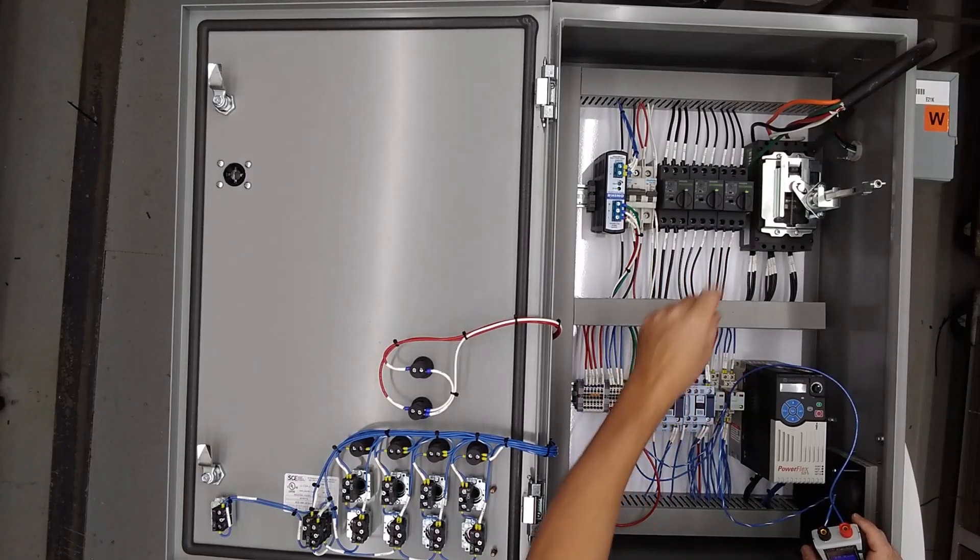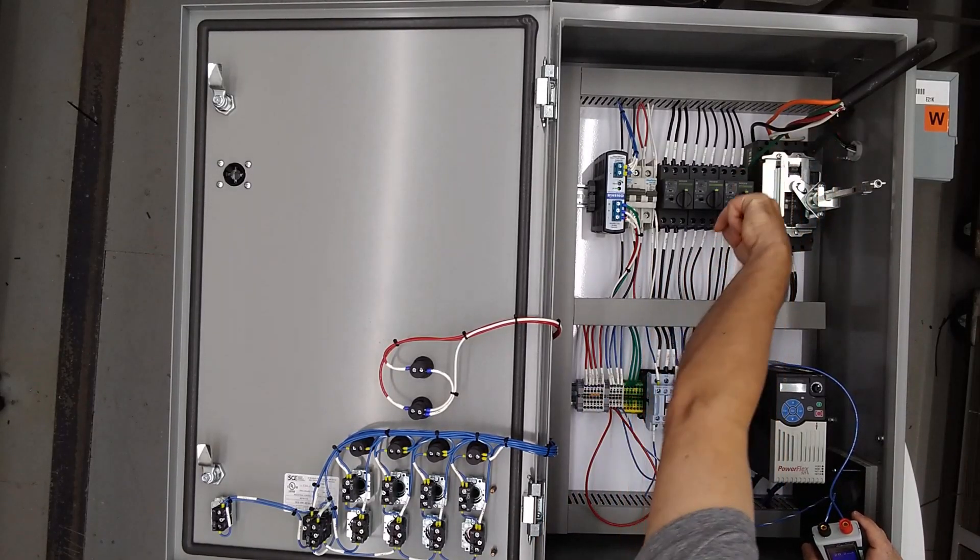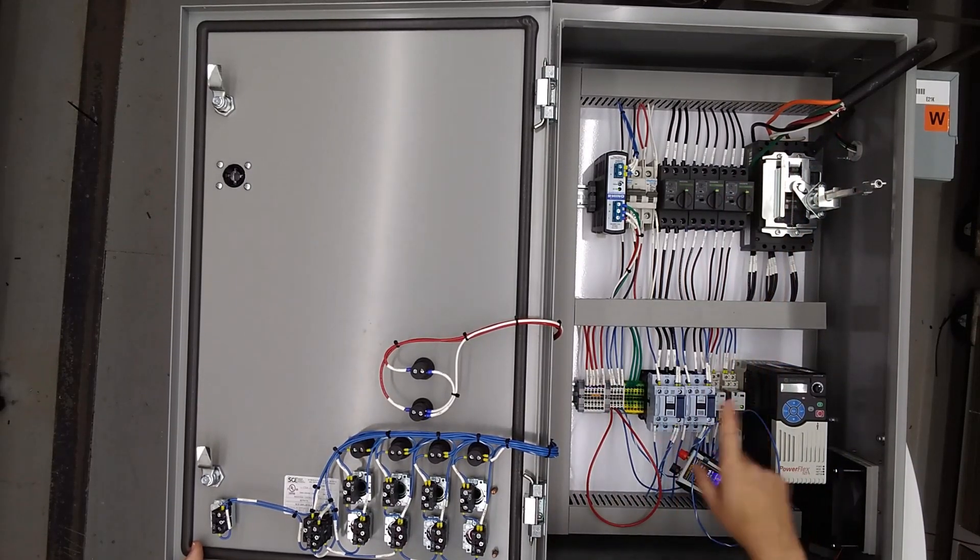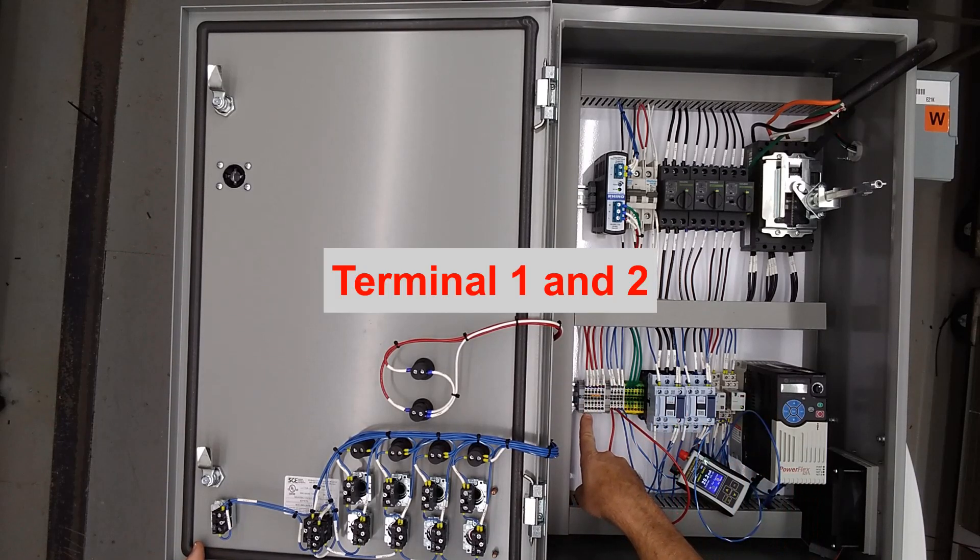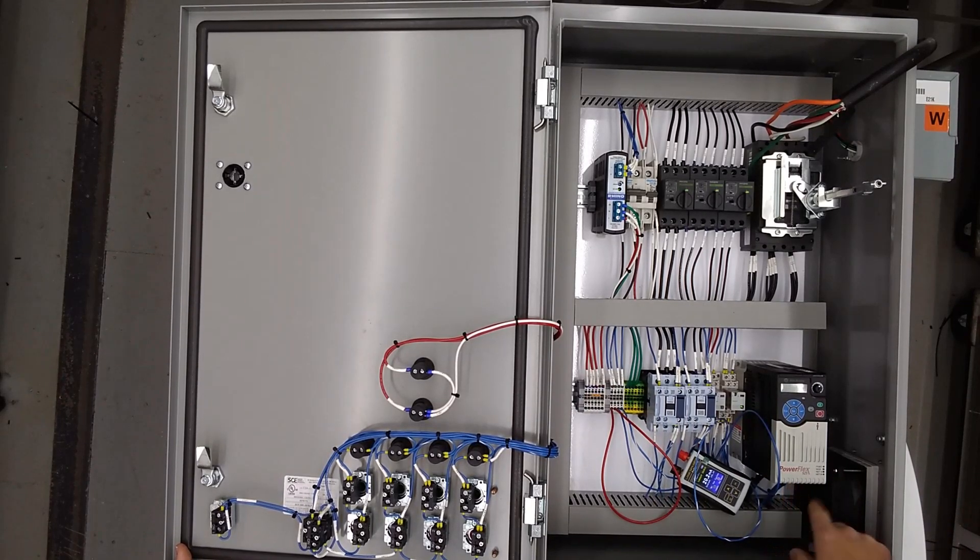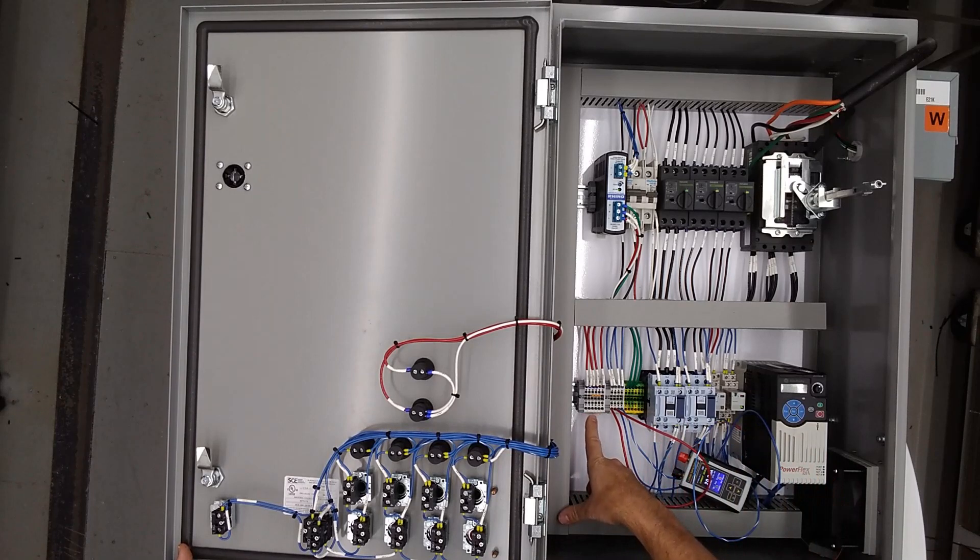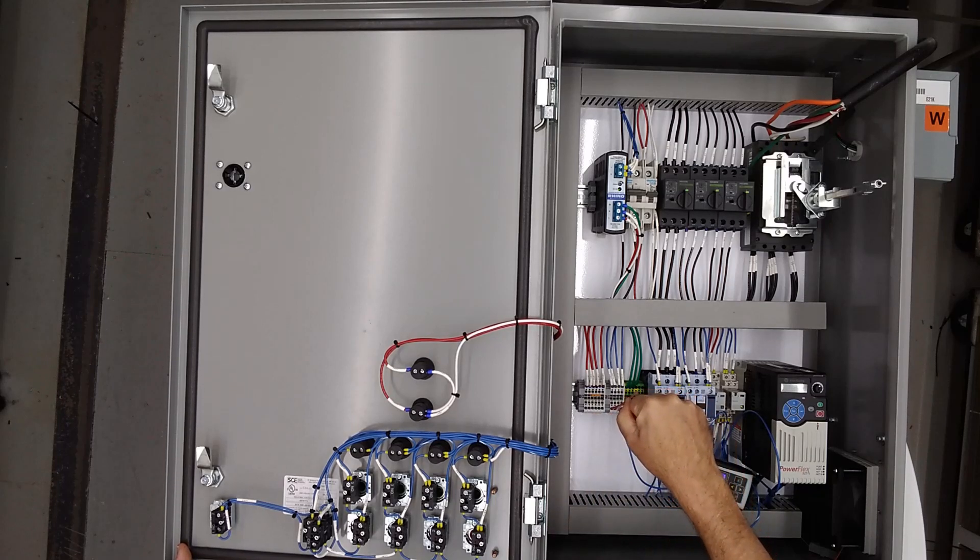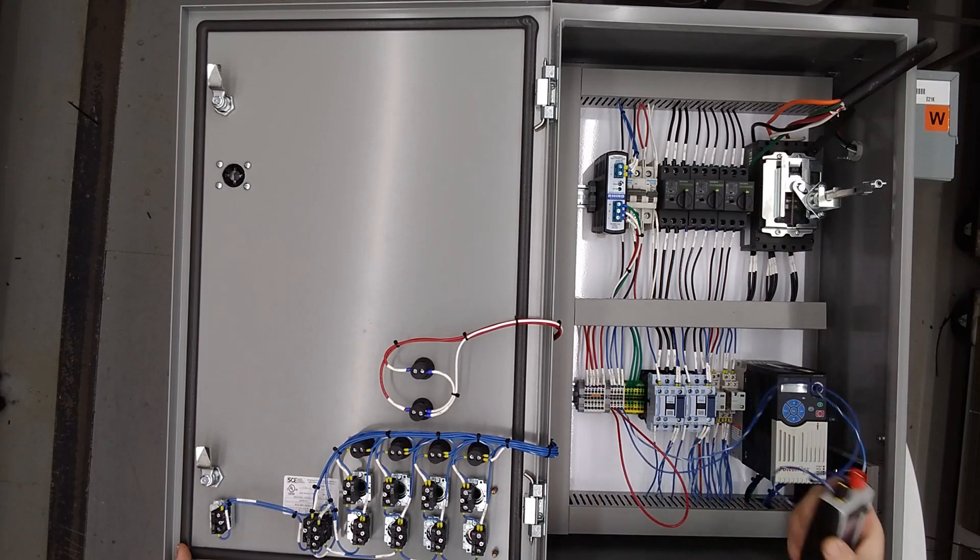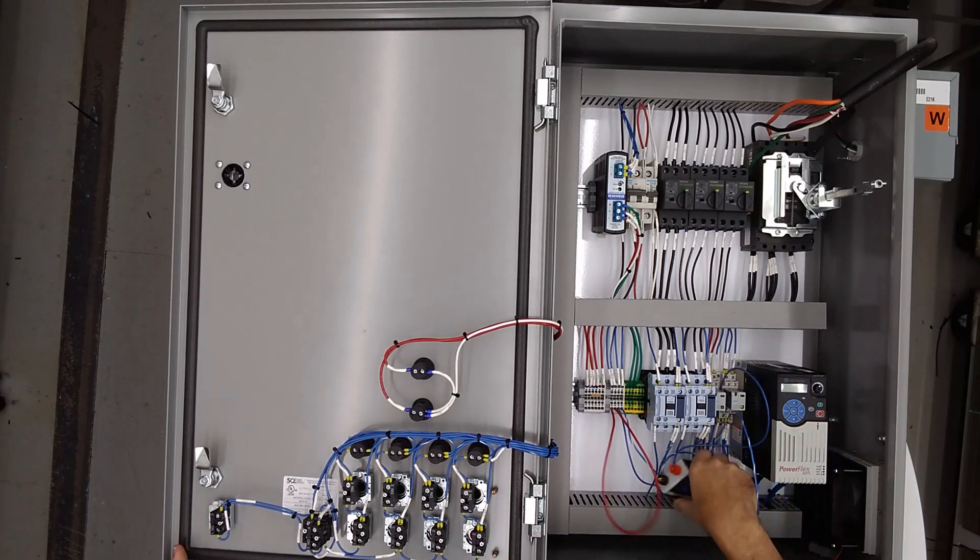So as far as connections, you'll connect 480 volts to the top of the breaker. Your ground goes there. Your screw conveyor goes in the bottom of this contactor. Aeration goes into the bottom of this contactor. Your dust collector is terminal one and two right here. Your cement feeder connects to T1, T2, and T3 on the drive. Then your silo high is terminal three and four. Your silo low is terminal five and six. Your remote cement feeder run is seven and eight. And your analog signal, which is a four to 20 milliamp goes to nine and 10.